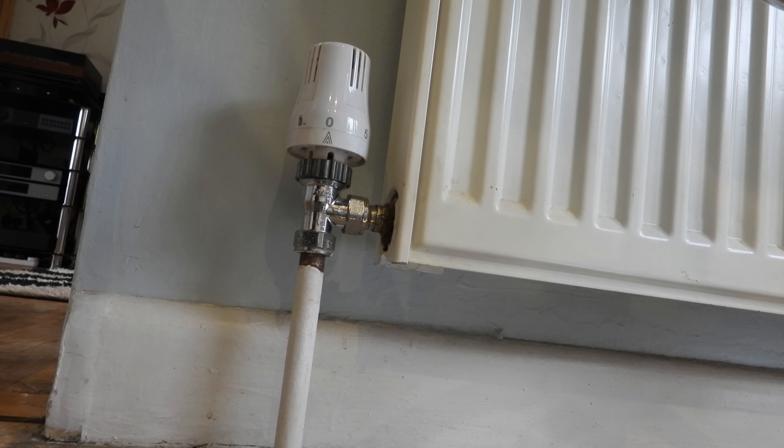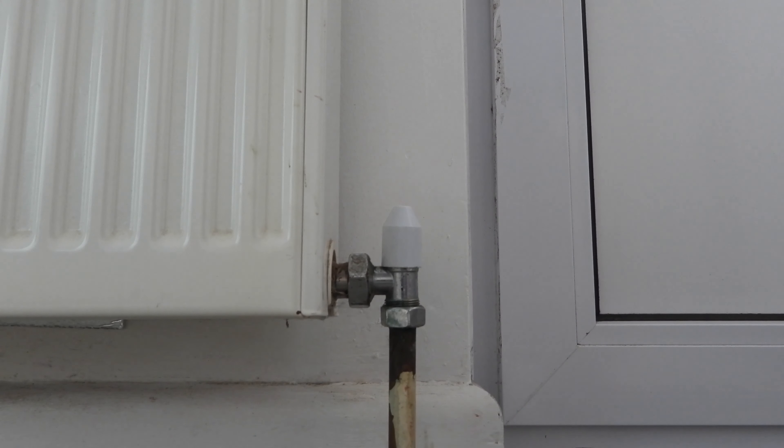If it's not getting cold and it's staying hot, well unfortunately these radiator valves you can't fix them. They have to be renewed once they don't work anymore. So how do we now turn this radiator off? We turn to the other end of the radiator and use the lockshield valve to shut it down if you're suffering too much heat from a radiator.